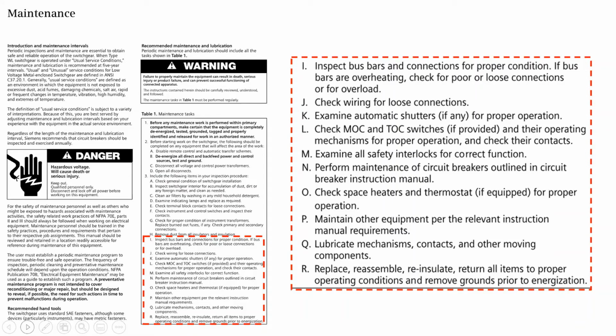Which is not today's discussion. But breakers generally don't just, as long as you operate them, you got to open them, you got to close them. If you let them sit there 20 years, what's going to happen? The grease on the blades is going to dry up, and those blades are going to get stuck in the holders. And when it goes to trip, it's just going to lock up and it won't open. So you got to open them, you got to close them, right?